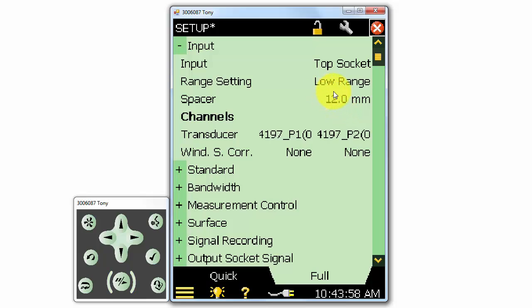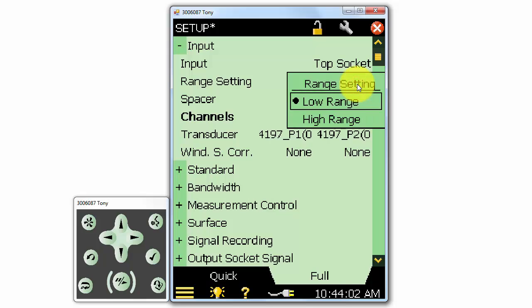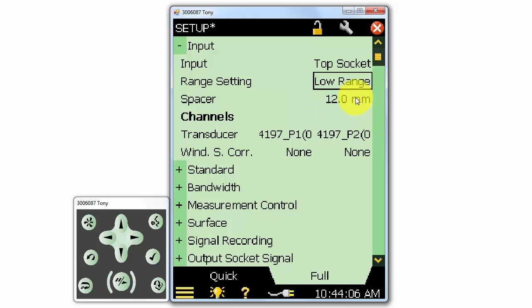We can also select the range setting. The sound intensity application has two ranges, high and low, for different levels of noise sources. If we are measuring a quiet source, we would use the low range, and if we have a moderately loud or louder source, we would use the high range.